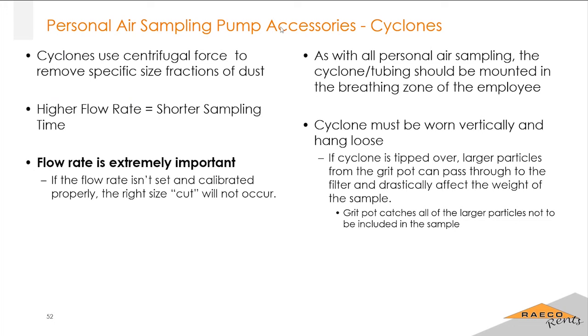Okay, yeah, so a little bit on the accessories like the cyclones I mentioned. Those are using centrifugal force to remove specific size fractions of dust. And if you're using a higher flow rate, you're usually going to have a shorter sampling time. Like I mentioned before, flow rate is extremely important. You want to make sure that that's calibrated properly.